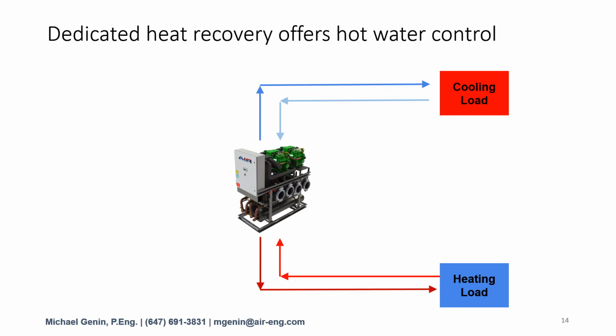The most simplistic example, a dedicated heat recovery chiller. A dedicated heat recovery chiller offers full control over the condenser hot water temperature. Since it's sized for the hot water load, it will always be able to maintain this load as the heating load ramps up and down. The chiller will not be able to control to the cooling load. If the cooling load disappears, the chiller can watch for this and unload its compressor. However, in that scenario, the amount of heat available will be reduced and eliminated.